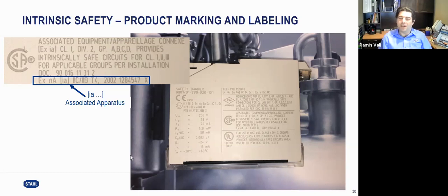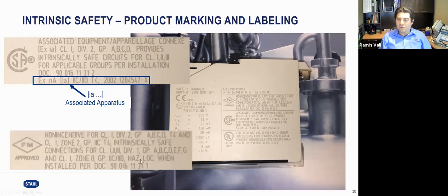NA means non-arcing. As Barbara mentioned, this device can be installed in zone 2 or division 2 because of NA. What we see in the bracket is IA. That means that this device works as an associated apparatus, and can be connected to zone 0, zone 1, or division 1 equipment. And the last, this one, yep.